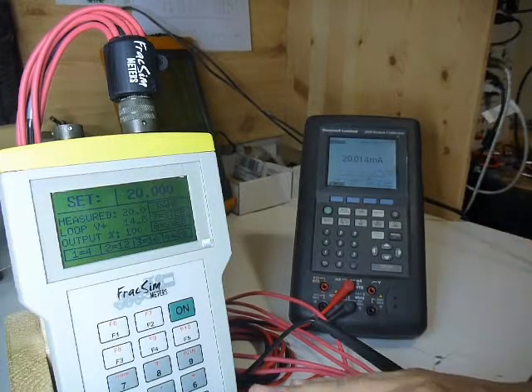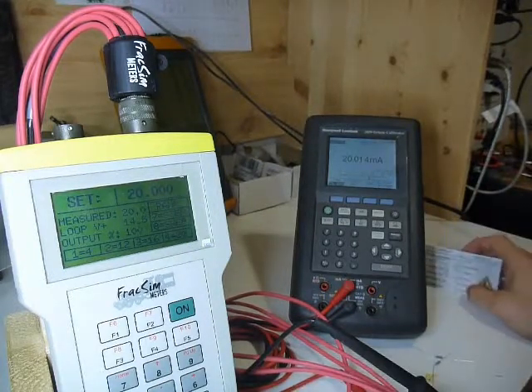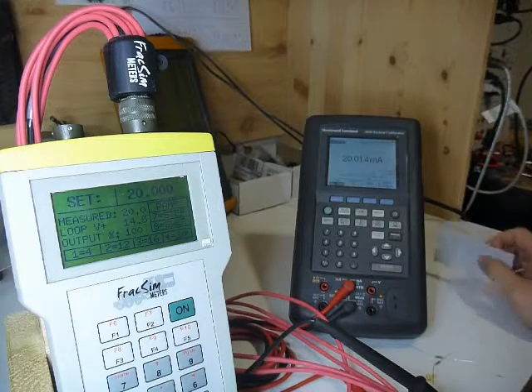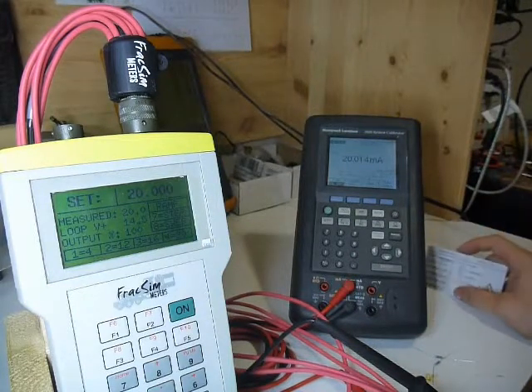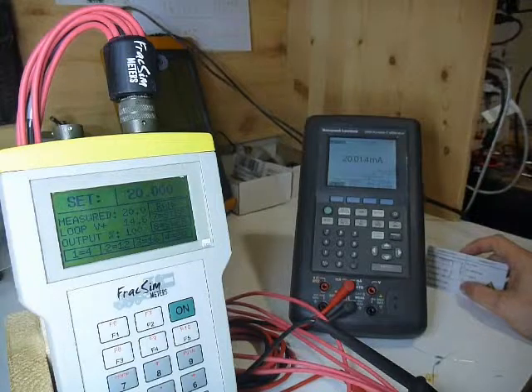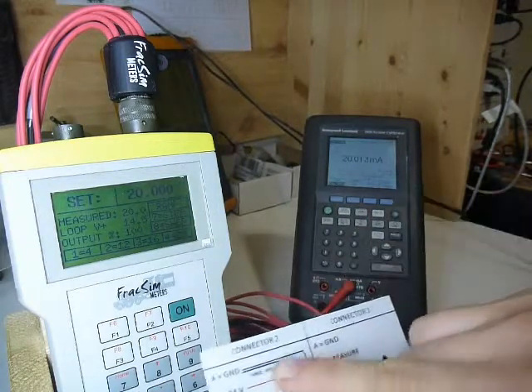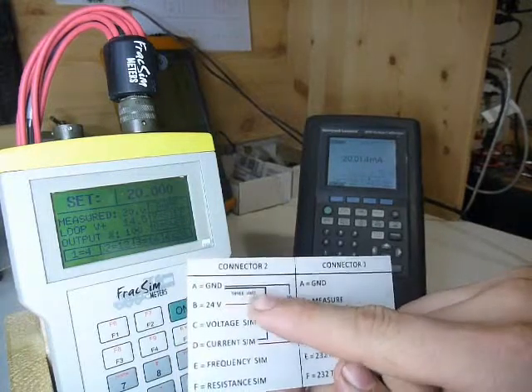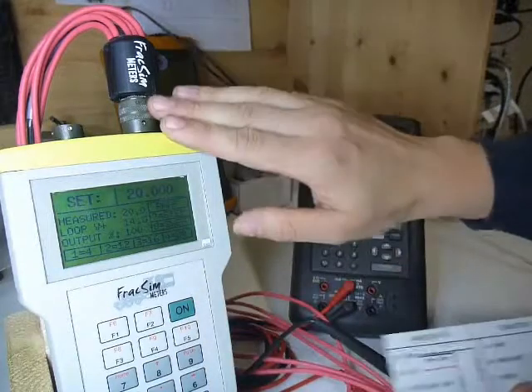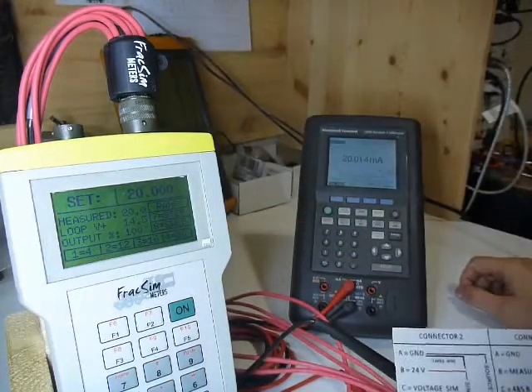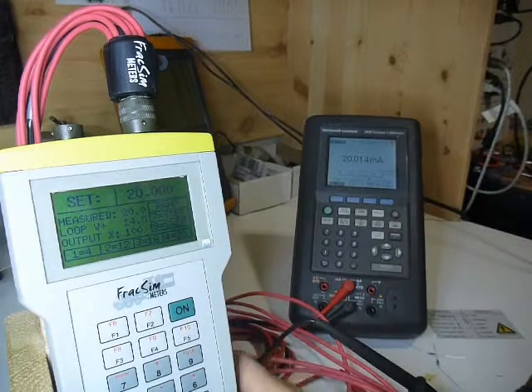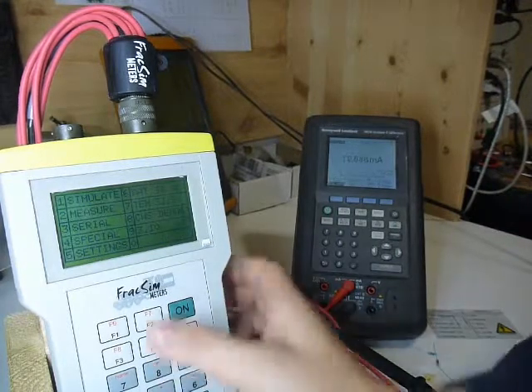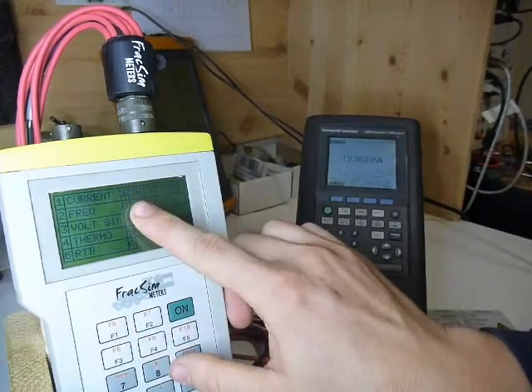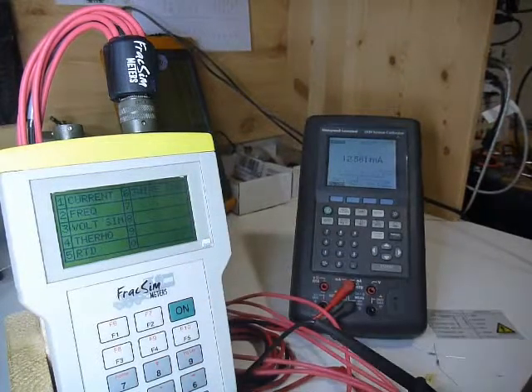So what I've done with the meter is I've integrated some bits and pieces so that you can actually measure all the voltages on the loop while you're simulating current. And that's why on here there's this 3-wire current sim. Basically it's the same as the sinking current, but you need that ground wire from the meter hooked up to ground on the unit. And it's a different menu. So I'm going to go back, go to simulate. Now up in the top you're going to see 3-wire current. So I'm going to press that.